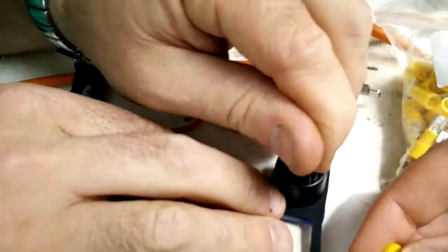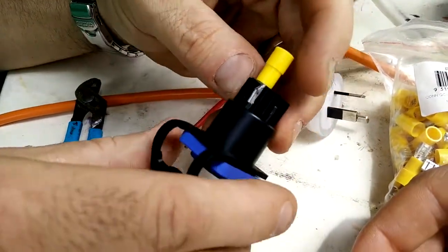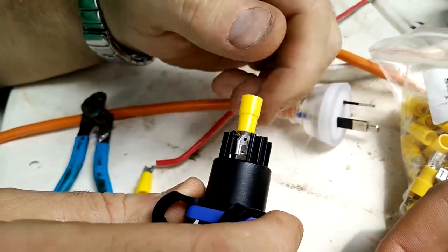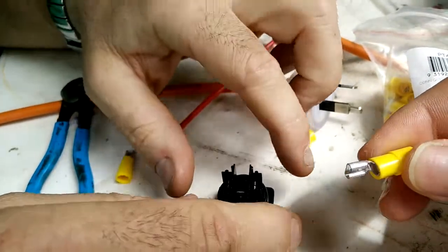So what James is doing here is he's just taking a little pair of pliers and he's just squeezing it just to make it so that there's less space between the flat and the crimping section. And so then it will provide positive pressure. And so then when you push it down, it's going to be hard to push on, but it also means that it's securely fastened when you try and pull it off. So that's what we've done. We recommend that you do it or you speak with your electrician and make sure that that's what they recommend.